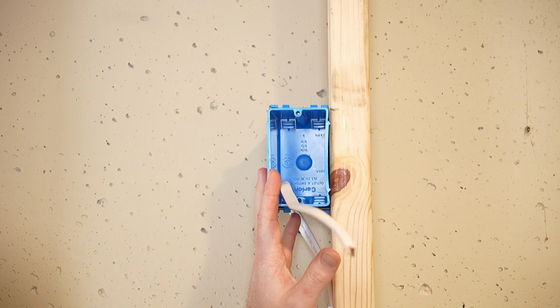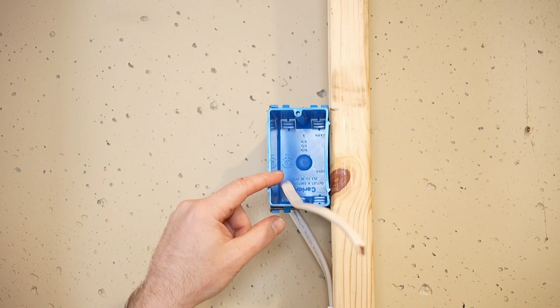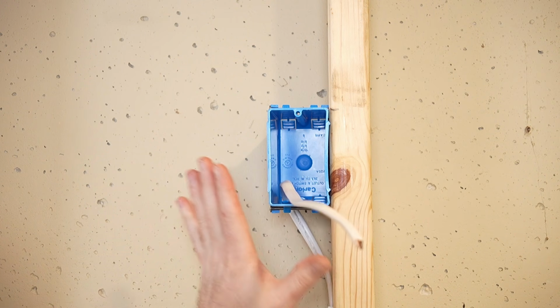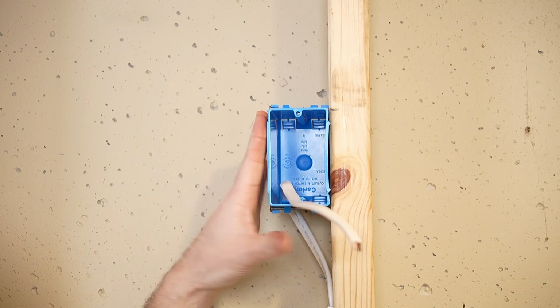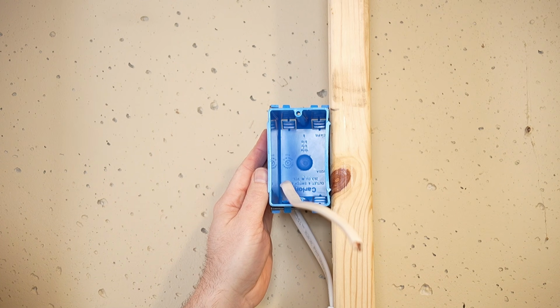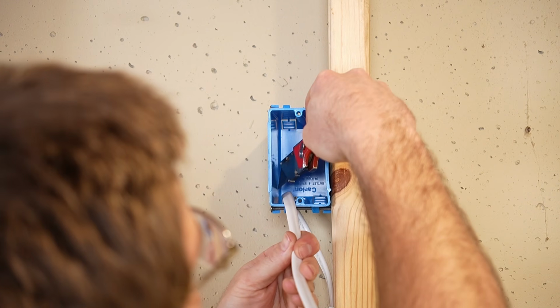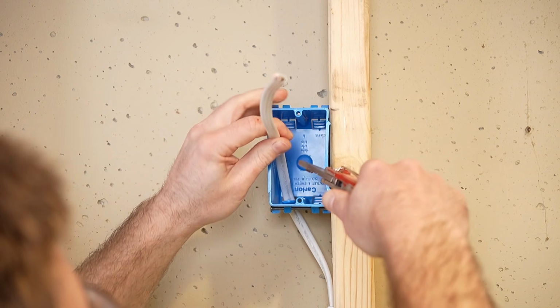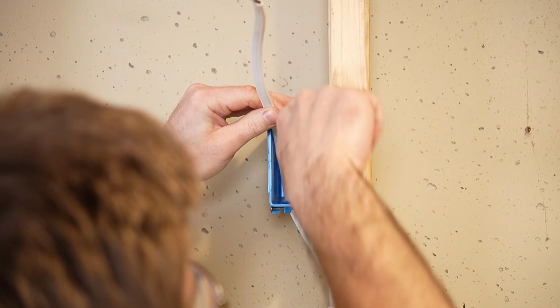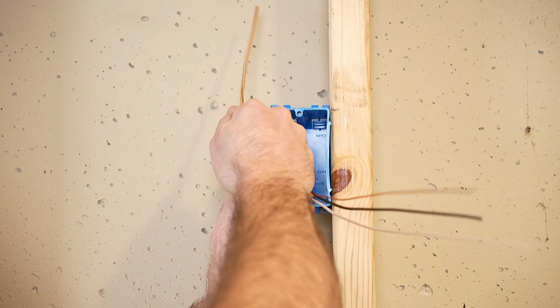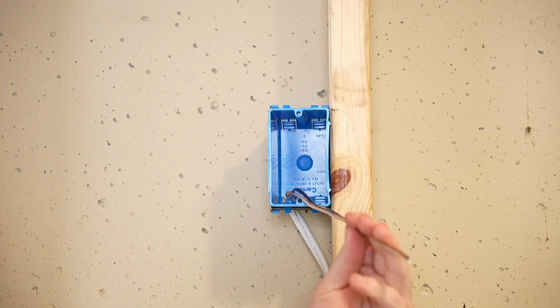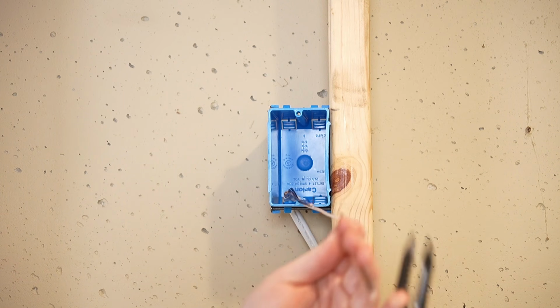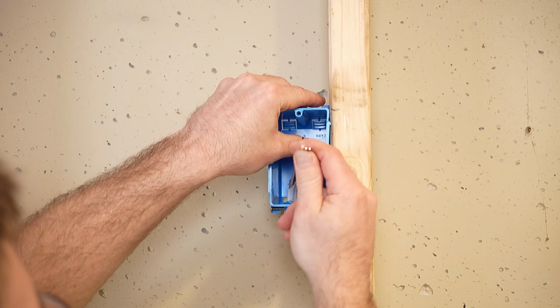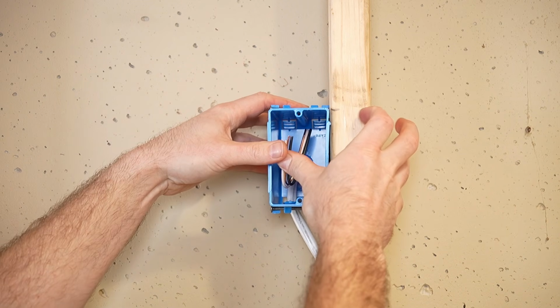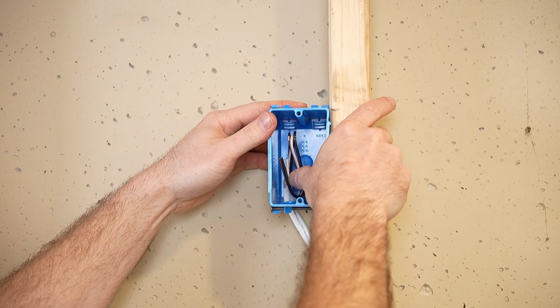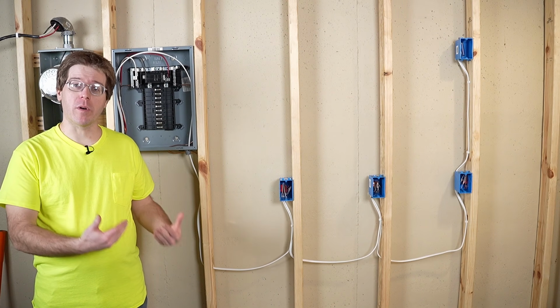And finally, at this upper box, there's really nothing that needs to be made up. We are gonna strip out this cable sheath, and then we're gonna tuck the wires into the back of the box to get it ready for that rough-in and sheetrock. Now, I am short, so let's see if I can see up here to do this without a stepladder. And I am gonna trim these wires up just a little bit. If you leave your wires too long in these boxes, it makes them more prone to getting caught by that roto-zip blade. And with that, we are ready for rough-in inspection.